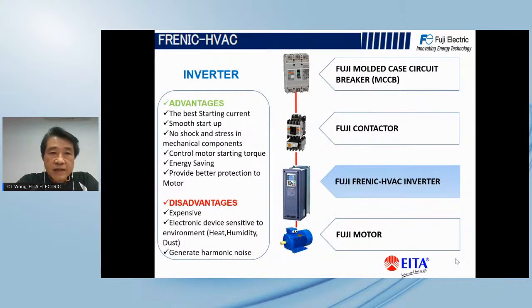The latest, I can say, is the inverter. The connection is still like a direct online: you need MCCB, contactors, inverters followed by the motor. This will be the best at this moment. The technology can help you lower the inrush current. As I say, later I will have a comparison on the tables. Less mechanical stress, high starting torque, able to have energy saving, better protections, but of course the cost is the most expensive compared with other starting methods.